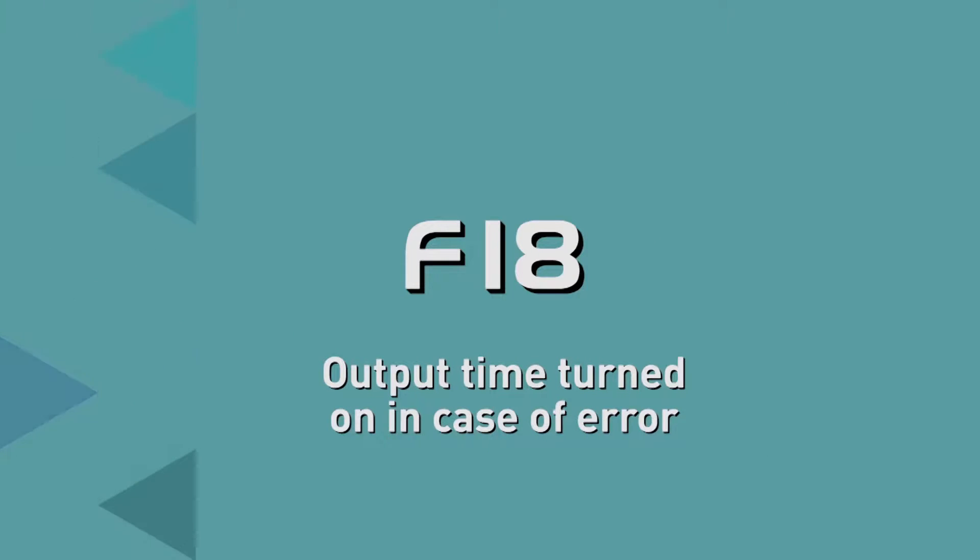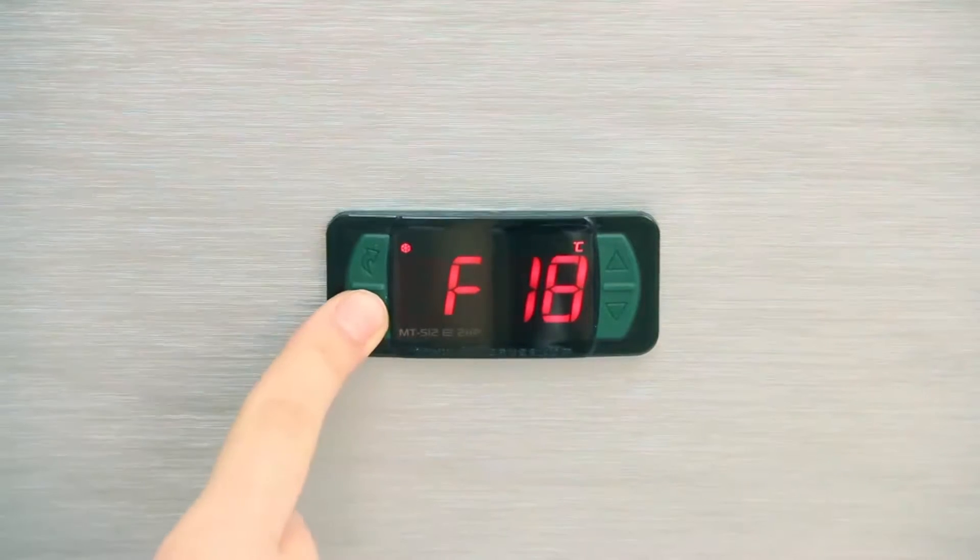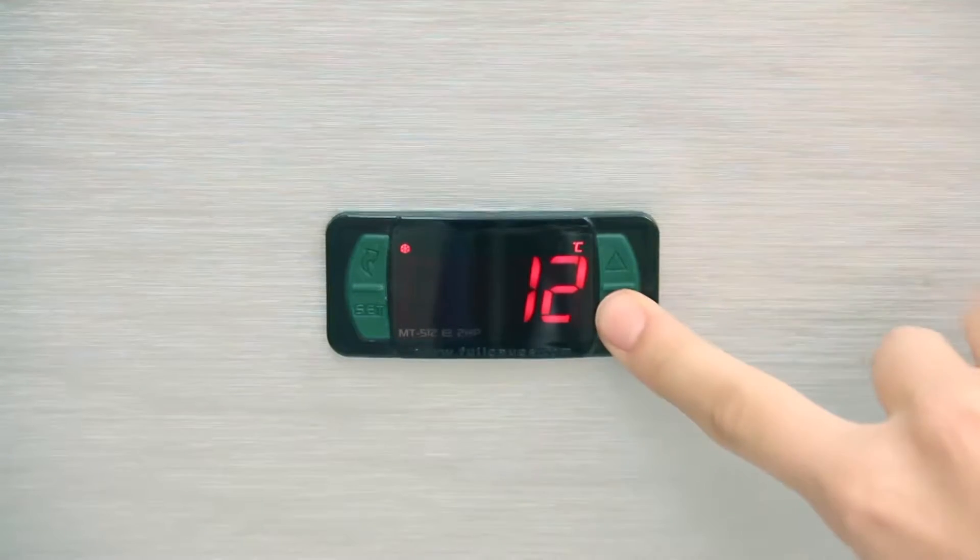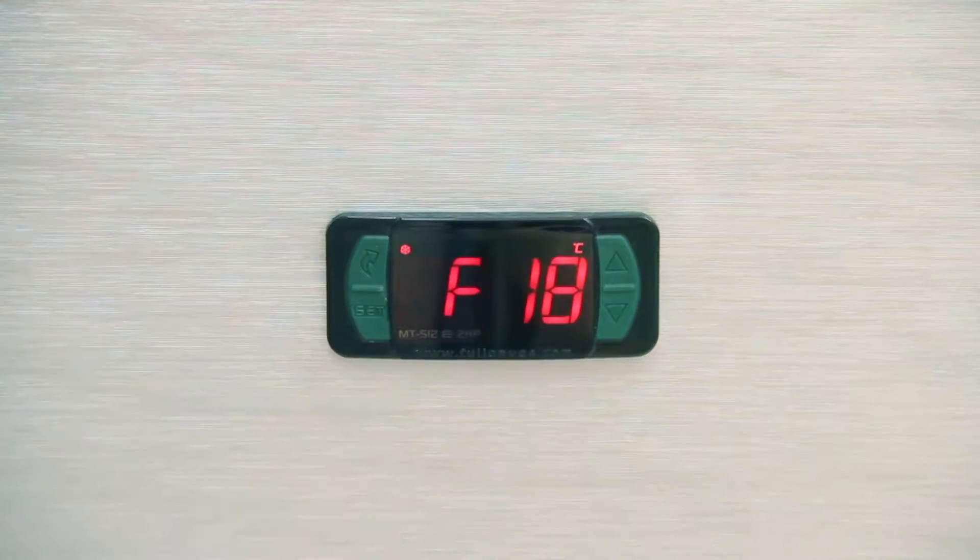F18, Output Time turned off in case of error. It sets the minimum time the compressor will stay off if the sensor is disconnected or out of the measurement range. In the example, we opted for an increase of 10 minutes.